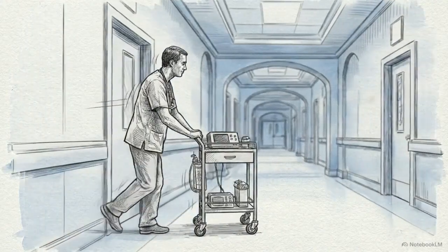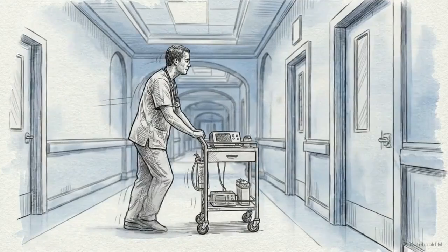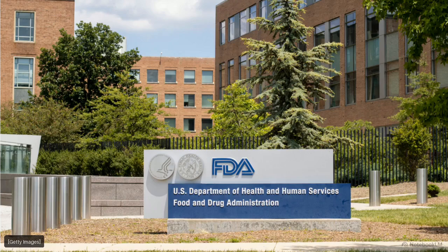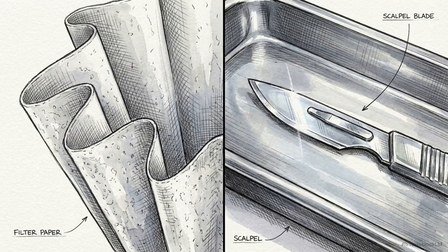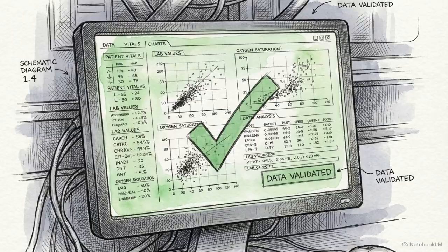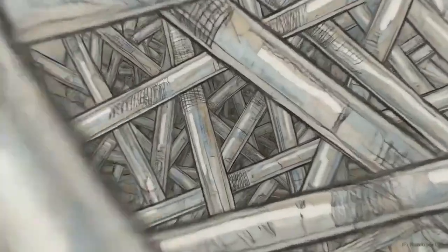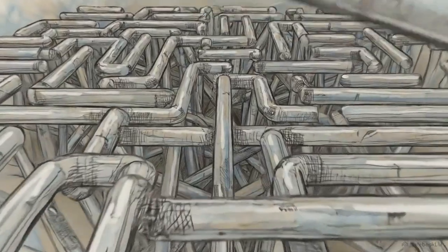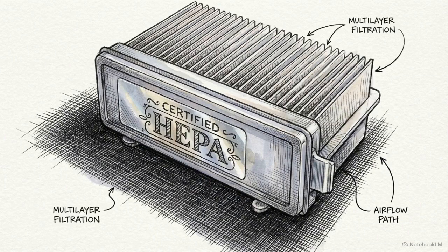If a manufacturer explicitly claims their system prevents airborne diseases or blocks viruses in a clinical setting, the standard rules do not apply. The Food and Drug Administration steps in, classifying those specific air purifiers as Class II medical devices, holding them to the same regulatory scrutiny as surgical equipment. These companies are legally obligated to secure a 510(k) clearance. They must submit hard data proving their glass fiber labyrinths successfully hit these extreme federal benchmarks in clinical environments. A HEPA label indicates that a filter has met a strict federal benchmark, proving it can successfully navigate the physical complexities of the microscopic world.